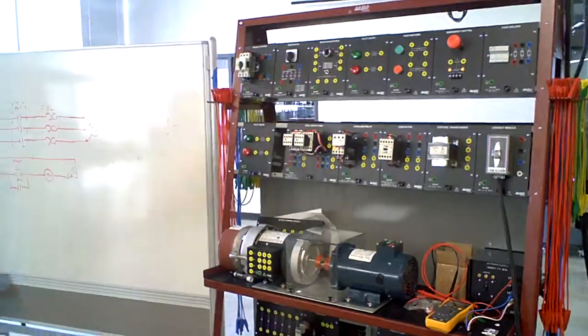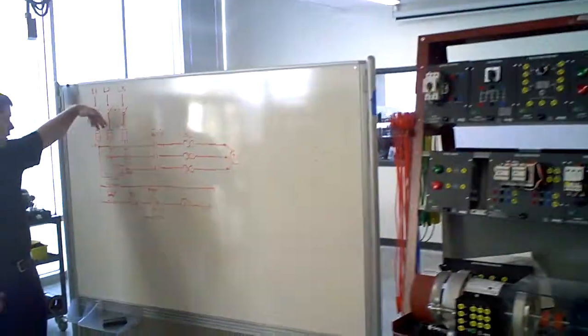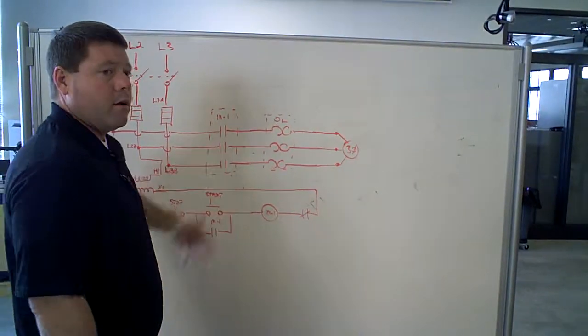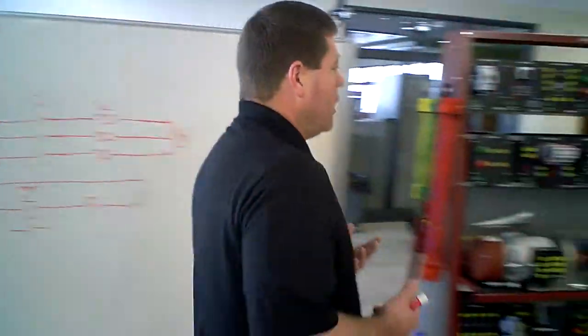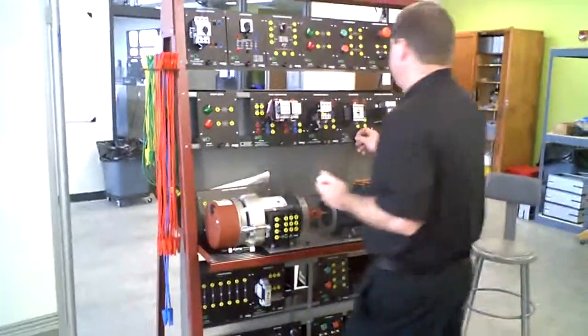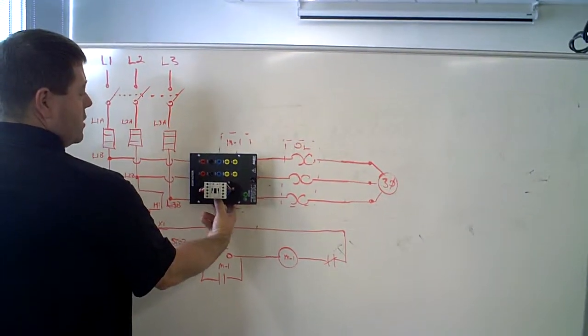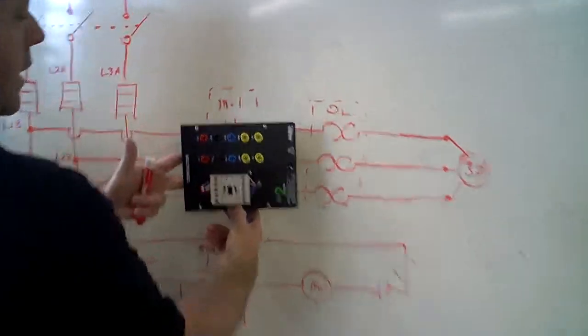So the next device here, the three legs come in, line one, two, and three come in. They disconnect through your fuses, and then they go out to your contactor. Your contactor, the purpose of the contactor is to close contact and send voltage to your motor. So you're going to have line one, two, and three come in. Line one, two, and three go out.